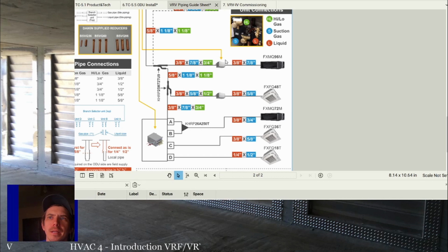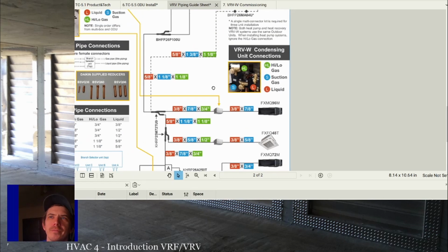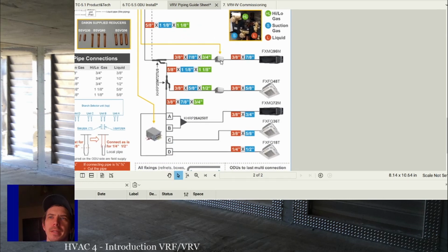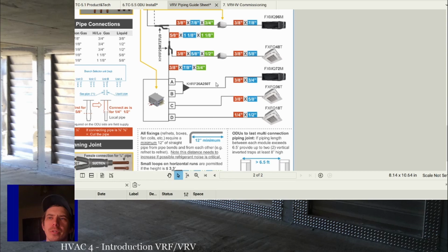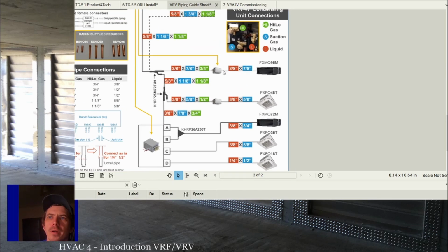And then that wire is going to daisy chain to all the branch selectors. So you'll have 2 wires going to this one, and then those 2 wires will continue and go to this one, and those 2 wires will continue and go to this one, and they just daisy chain on. And then from the branch selector, it'll go to the indoor unit, and then from the indoor unit, it'll go through to the thermostat. Generally, that's how it ends up working out.